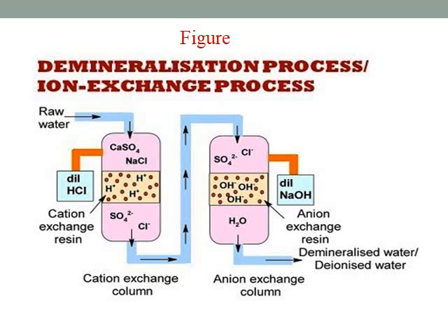First one is a cation exchanger bed, which is attached with a dilute HCl unit, and we will come to know how we can regenerate this exchanger bed by passing dilute HCl. This is a regeneration chamber, and the second one is fitted with an anion exchanger bed, which is connected to dilute NaOH for regeneration, and water is passed through these sealed drums.